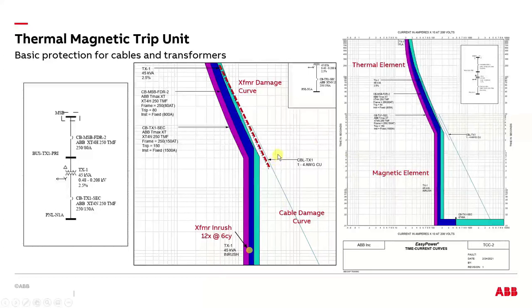So the point I was making with this is that the thermomagnetic breakers, if applied correctly, are perfectly capable of providing good protection for basic components. This is an interesting thing, this inrush, where the blue breaker has to clear it and the purple breaker, it doesn't matter. But this inrush, these have become a lot larger over the years. Back 6-7 years ago, people were using an 8x number for this. Well, now with these new transformers that are compliant to the new DOE energy code, that number has jumped from 8 to 12, which has become problematic in some cases because the normal breaker that you'd use to protect that transformer has too low of an instantaneous and may or may not trip when you energize that transformer. So that's another discussion for another day, but thermomags can take care of that. It just has to be sized correctly.